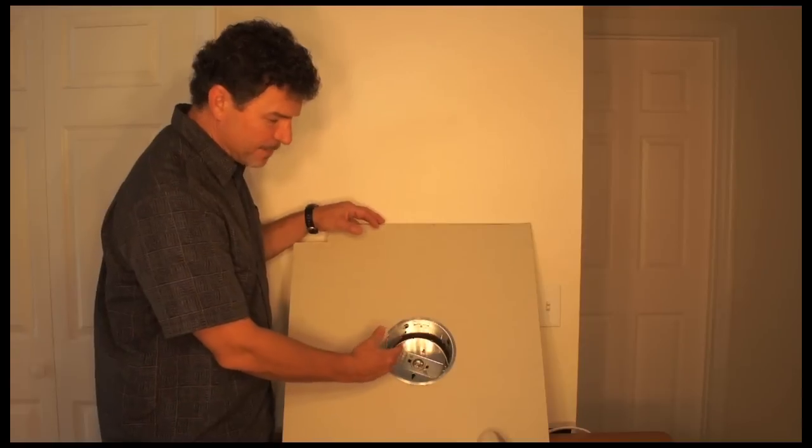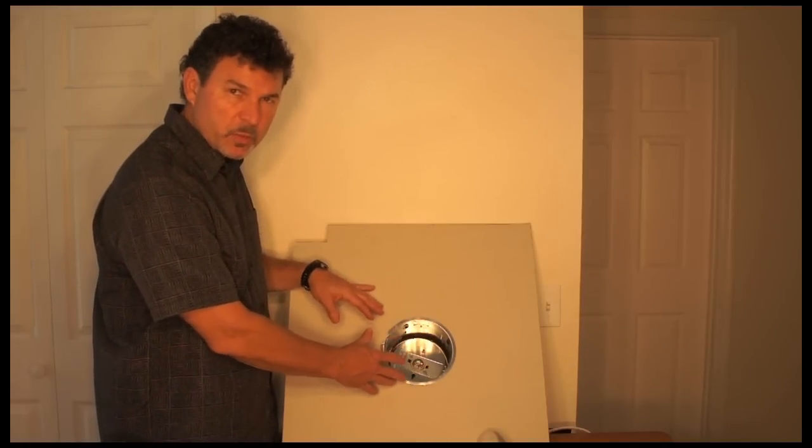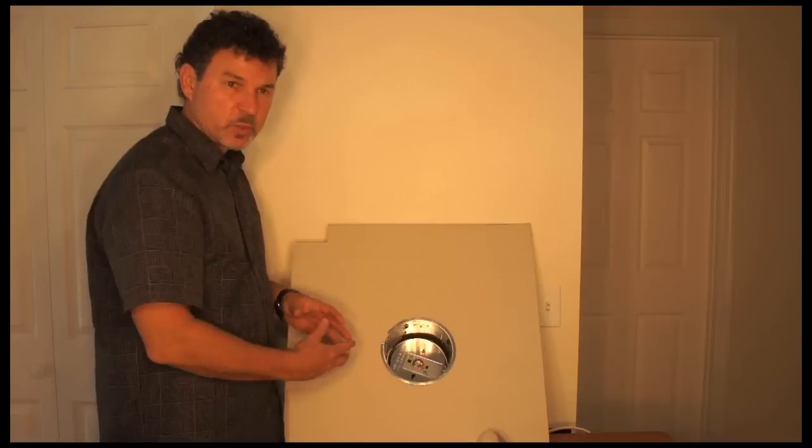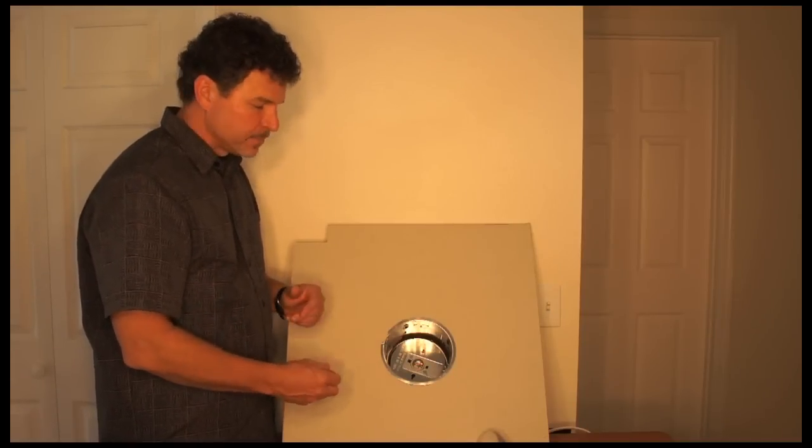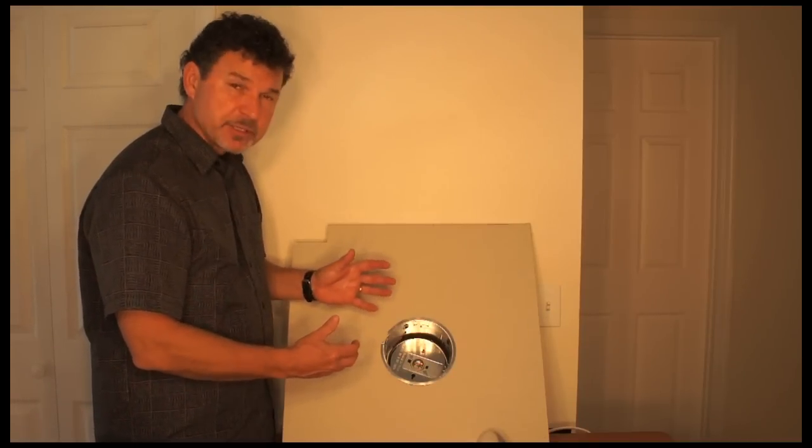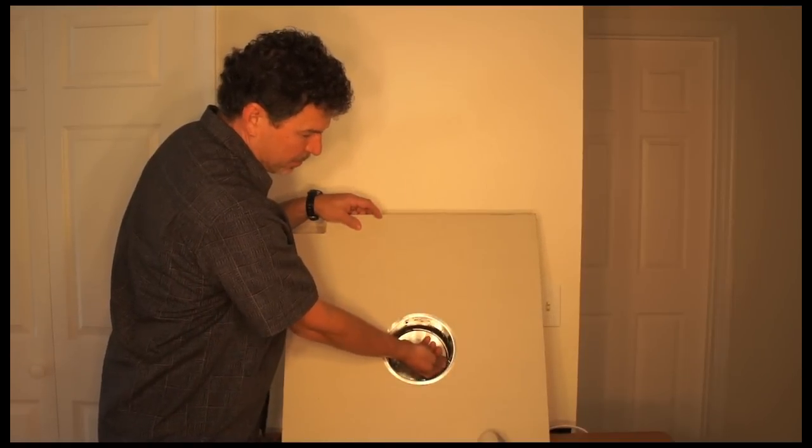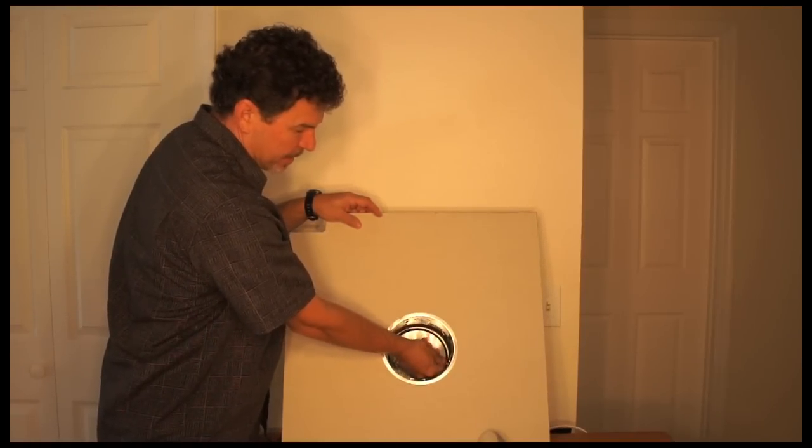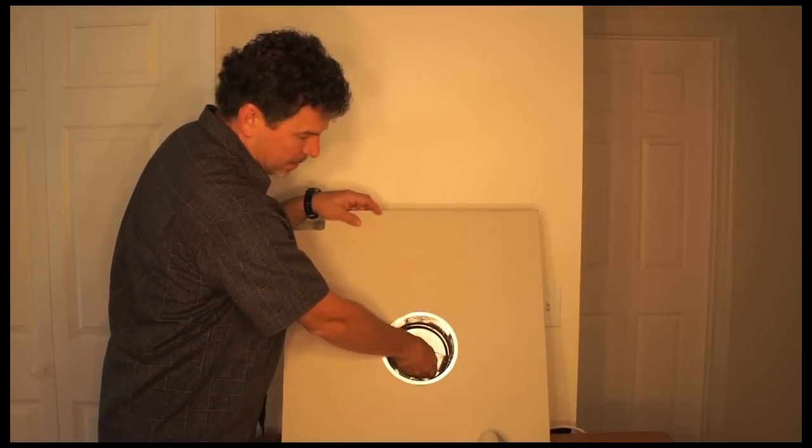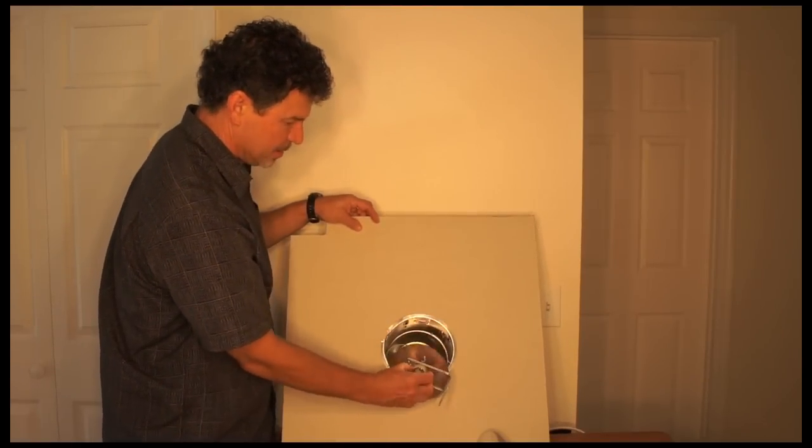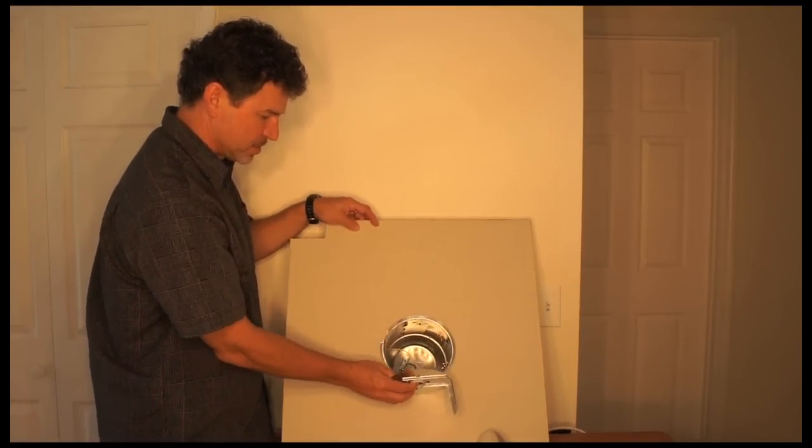The majority of the time, what will be wrong with the recessed fixture is the socket inside. The socket will either be worn or go bad, so we're going to replace it. In order to do that, I'm going to pull this socket down by unscrewing the wing nut, and here I have the socket exposed.